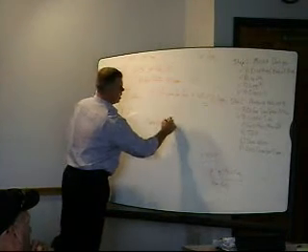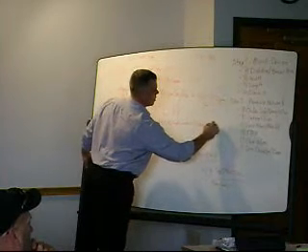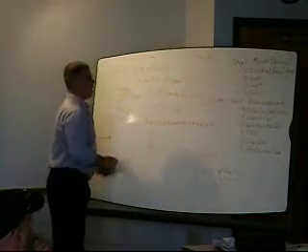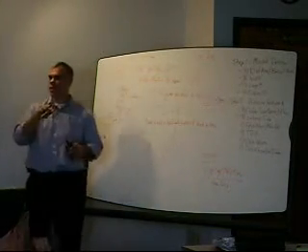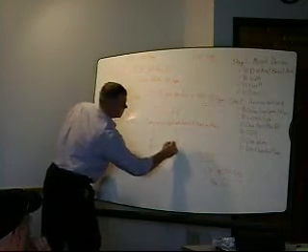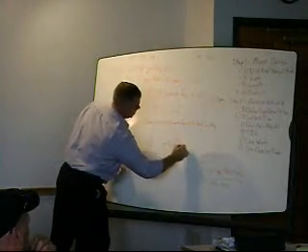TDH is pipe loss, which we just did, plus network loss, plus elevation head. We got this one already figured out, 4.9. The network losses, both of those manuals give you a pretty straightforward, simple way to figure that. It's in the formula. I won't pull it up. You take your head times 1.3. And that gives you the losses.